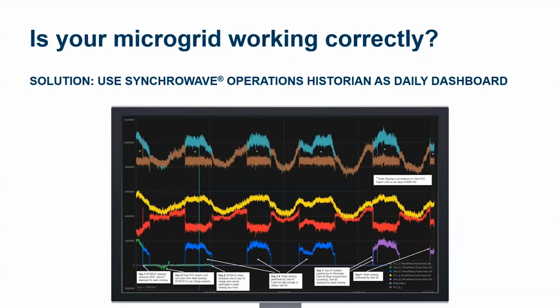And you can see some interesting things happen. This is time synchronized at the relay. So there's no debating that this data is correct because it is correct to the millisecond. And it is time synchronized with technology called C37.118, native to the SEL relay. Built for a much bigger challenge, but perfect for the microgrid market. And now Synchrowave Operations being very affordable, it is the optimum historian for the microgrids that we deploy. Here in the bottom, in this particular case, it shows something very interesting. And as an example, the green happens to be a battery-backed inverter of approximately 4 megawatts.